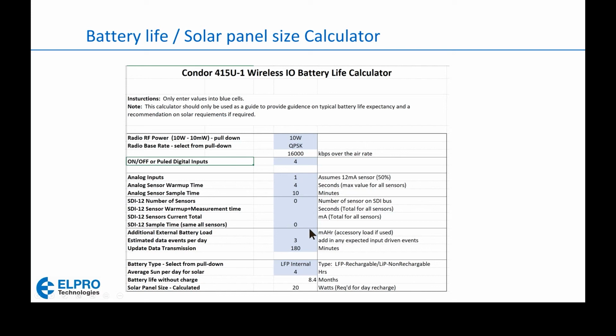Okay. Then just showing this one right here. We've set this guy up so that it's going to update every 180 minutes if none of the discrete values change state. We're expecting 3 event-driven events per day. And that brings us down to this calculation right here.